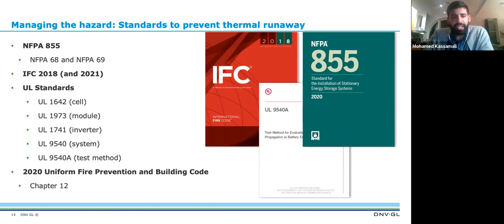The UL 9540A test is not a pass or fail, there's no such thing as passing it and getting a certification. What it really serves as is a data collection and observation exercise that allows energy storage manufacturers, integrators, and developers to better design their systems to be safe, using the inputs of understanding the hazards of thermal runaway and the off gases or fire that can emanate from a thermal runaway event.